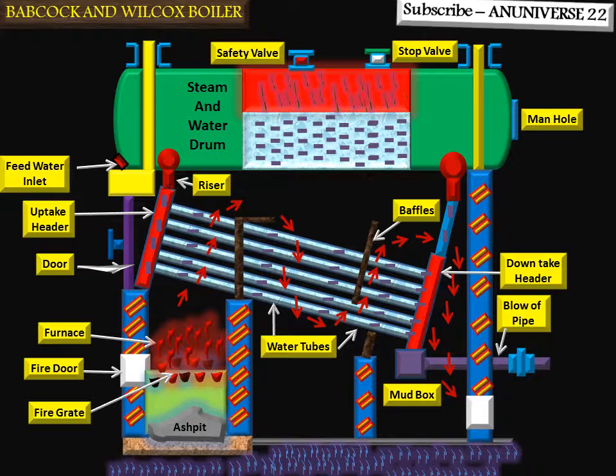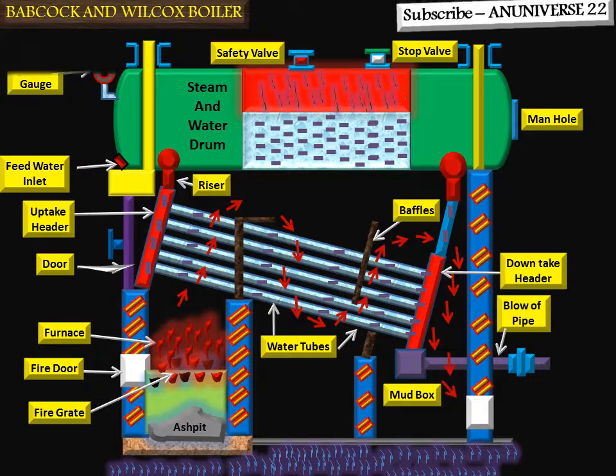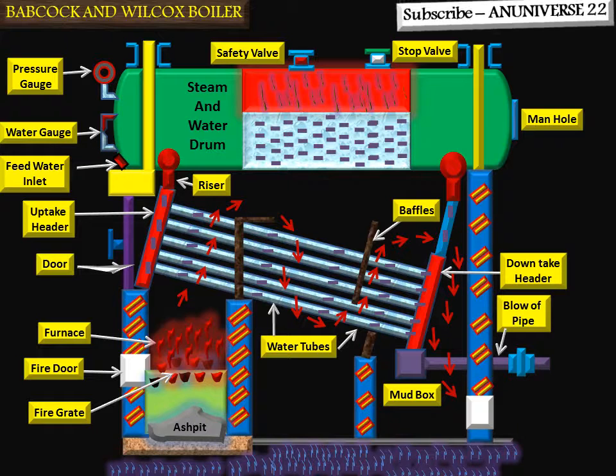This is the stop valve, fitted at the highest part of the shell or drum. Its function is to control the flow of steam from the boiler to the main steam pipe and to shut off the steam completely when required. The pressure gauge is used to measure the pressure of steam inside the boiler and is fixed at the front of the steam boiler. The water level indicator is a glass tube, generally two in number, fitted in front of the boiler to indicate the level of water inside the boiler to an observer.